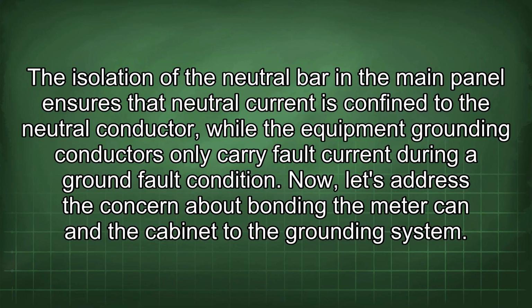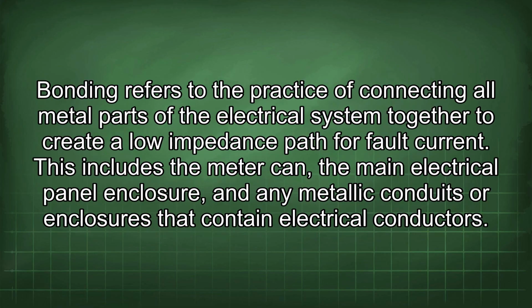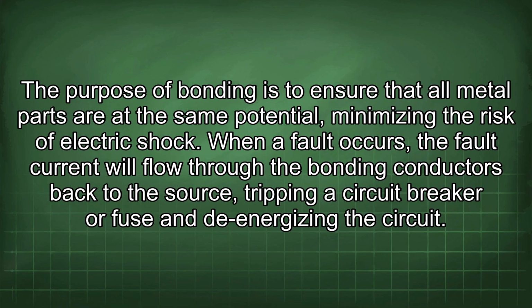Now let's address the concern about bonding the meter can and the cabinet to the grounding system. Bonding refers to the practice of connecting all metal parts of the electrical system together to create a low impedance path for fault current. This includes the meter can, the main electrical panel enclosure, and any metallic conduits or enclosures that contain electrical conductors. The purpose of bonding is to ensure that all metal parts are at the same potential, minimizing the risk of electric shock. When a fault occurs, the fault current will flow through the bonding conductors back to the source, tripping a circuit breaker or fuse and de-energizing the circuit.